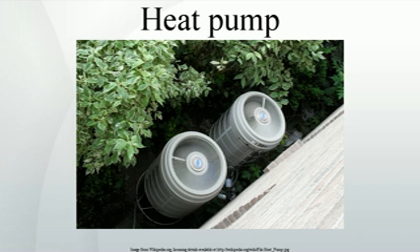In particular, the pressure difference must be great enough for the fluid to condense at the hot side and still evaporate in the lower pressure region at the cold side. The greater the temperature difference, the greater the required pressure difference, and consequently the more energy needed to compress the fluid. Thus, as with all heat pumps, the coefficient of performance, the amount of thermal energy moved per unit of input work required, decreases with increasing temperature difference.